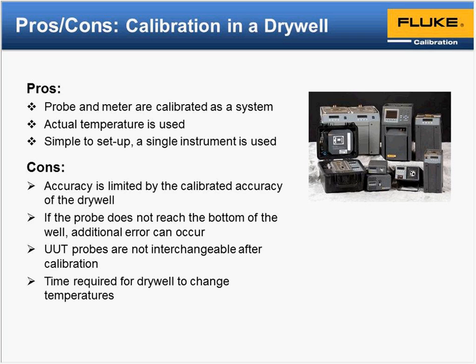And again, one of the cons we discussed is if you've got a unique situation where your probe is not able to be fully immersed into your well, that can add some additional error that's really hard to quantify. And then with any system calibration that you do with a probe and readout, once you mate them and make adjustments, they're kind of mated for life.